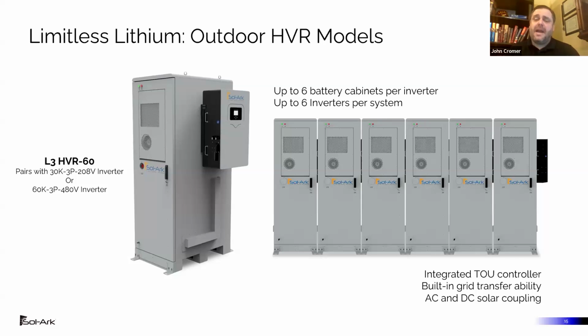We include the combining bus bar when you order the outdoor solution. And essentially, if you get any larger than 6 inverters and 6 battery cabinets per inverter in an outdoor setting, that's when you want to start building your own battery room and have a nice aggregated room where it might be a little bit more simple. You might have 1 air conditioner unit, not 6 air conditioner units. So our outdoor system is great, but for the incredibly large systems, you're probably going to use our indoor solution, whether it's inside the building or bringing your own battery room.